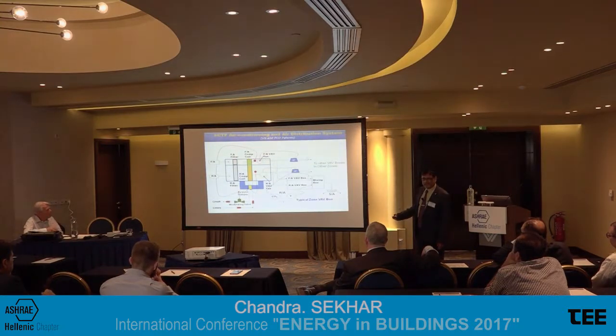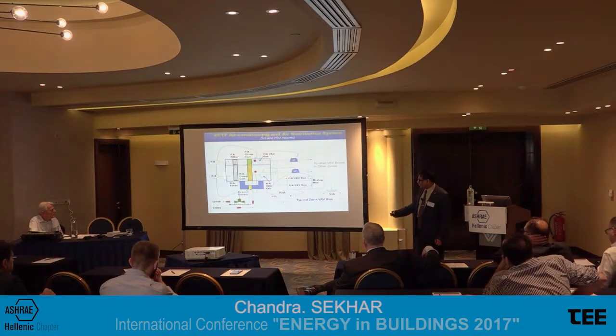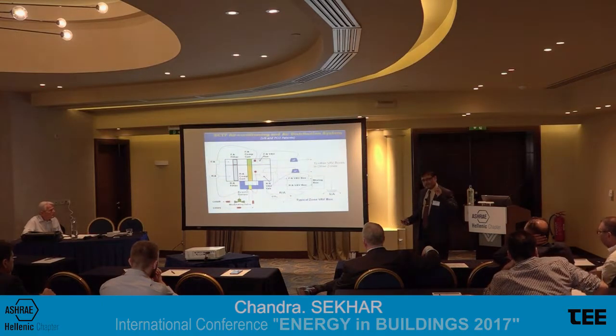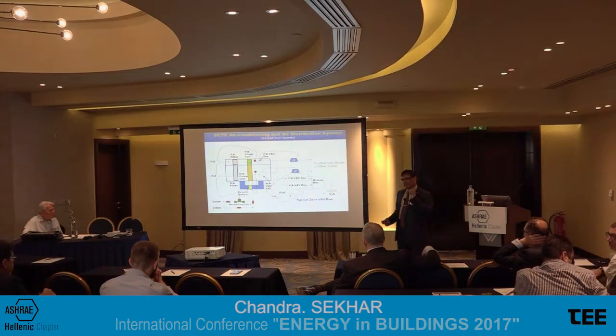We have a kind of a modified variable air volume box. And notice what's happening here. We have a local zone-specific temperature and CO2 sensor. The temperature sensor controls the recirculated air. This is for cooling. And the CO2 sensor controls the outside air. So the idea is demand ventilation being taken right up to the individual occupied zone.